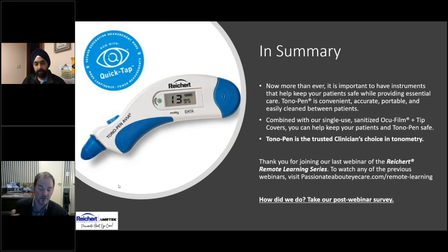Same thing goes for Tono-Pen. The older Tono-Pens that were made 20 years ago, first of all, are getting older and maybe need some service, but there have also been improvements over time to the way we analyze the signal and the way we average the results to make sure we're getting rid of outliers and so forth. So anytime anybody asks about variability or which one's more accurate, especially if they're saying, I have one that does this, it's really important to understand: is the instrument in good service? Are you using the correct tip covers, with specific reference to the Tono-Pen? How old is it? Has it been cleaned, calibrated, those sorts of things?